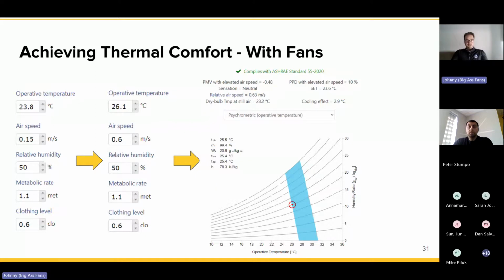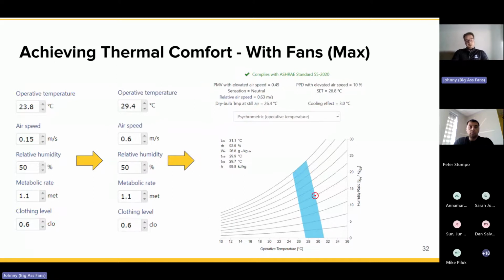So we've added fans that draw very little power, and we've reduced the usage of high intensity cooling mechanisms like an air conditioning unit. Let's push this a little bit further. So I've raised it to 29 degrees Celsius now, which in most office environments, people would be losing their marbles. I can tell you that because we work in one. And if someone sees the thermostat at 29, they would be not thrilled with that. However, if you actually just look at the math, they would feel the same sensation as if it was 23 with no airflow. So this just shows you how far you can push it.